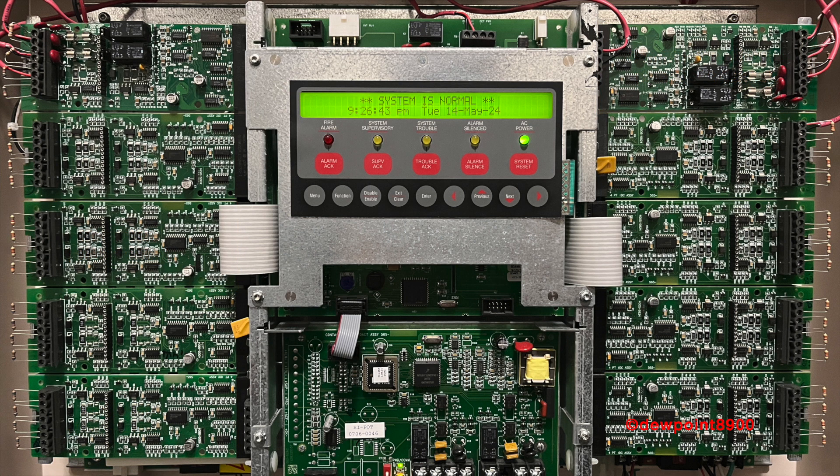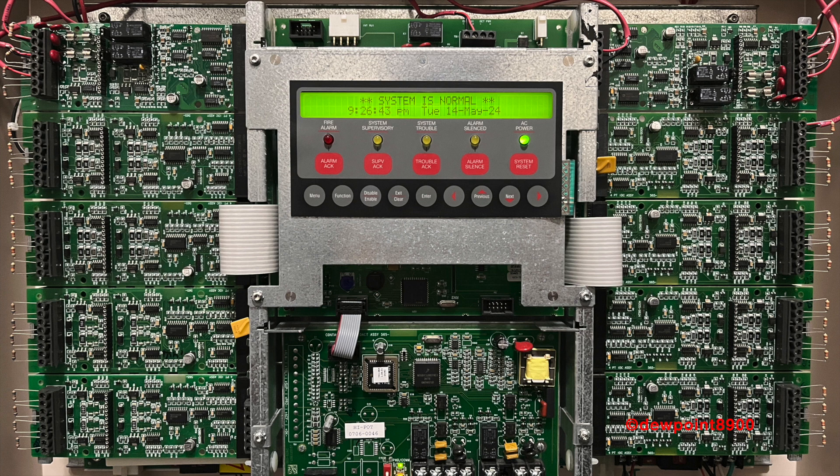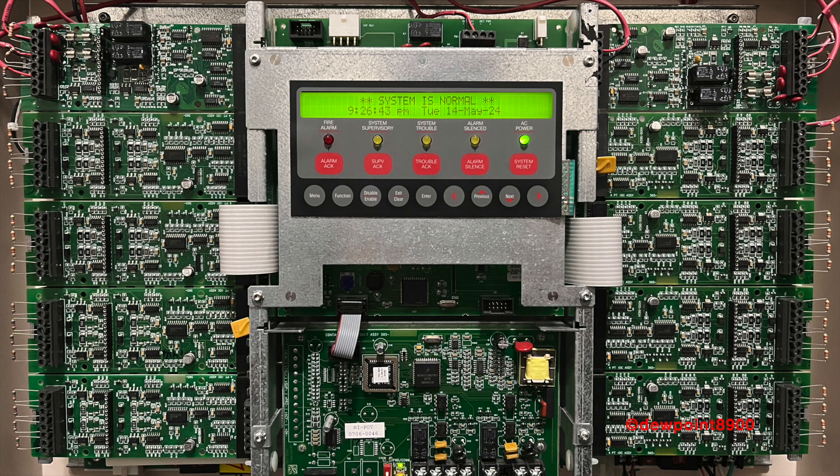A standard 4005 included two zone cards, a NAC relay card, and two spare slots on the right side of the back box. The layout can be expanded to five more slots on the left side of the panel. An expansion power supply will be mounted on the bottom left, along with an additional power distribution board. The 4005 can support a maximum of 36 zones or 38 NAC relays.